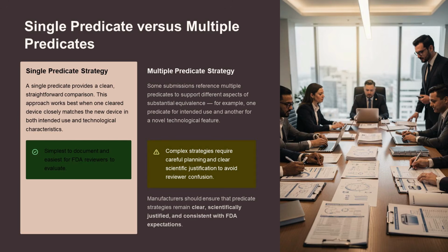Choosing between a single or multiple predicate strategy depends on the device's complexity. A single predicate offers simplicity, while multiple predicates may be necessary for novel technologies. Each approach must align with FDA expectations.